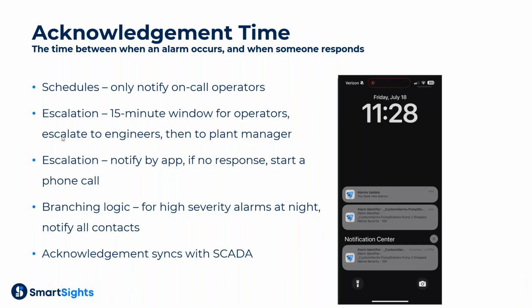Perhaps the most important part of a remote system that reduces acknowledgement time is that the acknowledgement in the remote system has to sync with the in-plant SCADA or other alarm systems, which SmartSights' solution does. So when an operator acknowledges an alarm by tapping the ack button on our mobile app, responding to the text message or email, or speaking into their phone on the phone call, that syncs into the in-plant system. People on the HMI, for example, can actually see that the alarm was acknowledged via voice call.